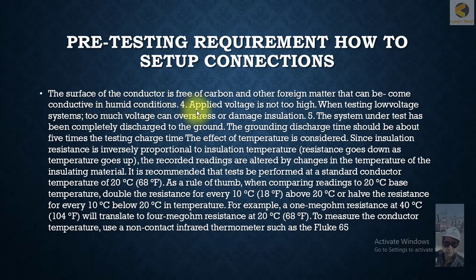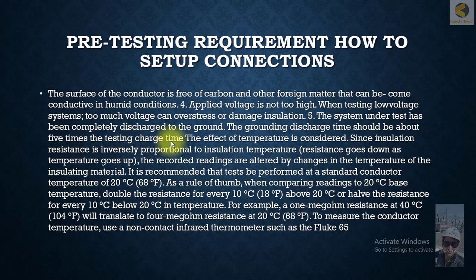The surface of the conductor should be free of carbon and other foreign matter that can become conductive in humid conditions. The applied voltage should not be too high — when testing low voltage systems, too much voltage can over-stress or damage the insulation. The system under test must be completely discharged to ground; the grounding discharge time should be about five times the testing charge time.